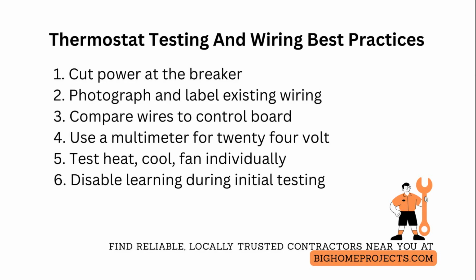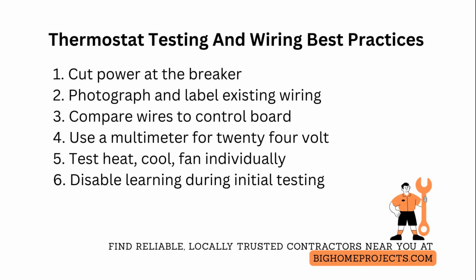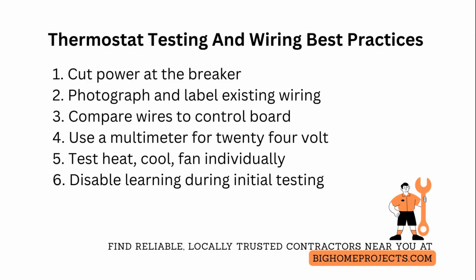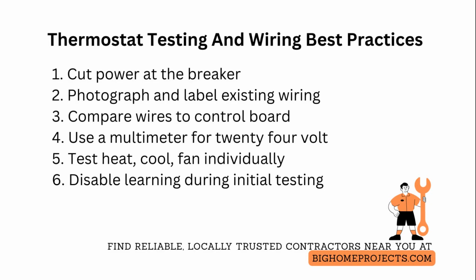If you have a heat pump, test the auxiliary and reversing valve commands and listen for clicking relays and compressor startup delays to ensure proper staging. Program fan on and fan auto, and verify the blower responds correctly to both signals.